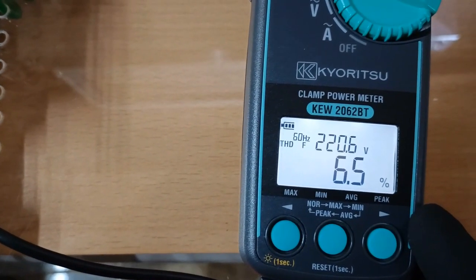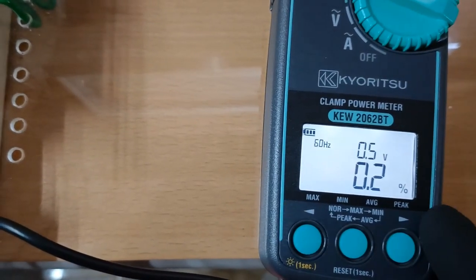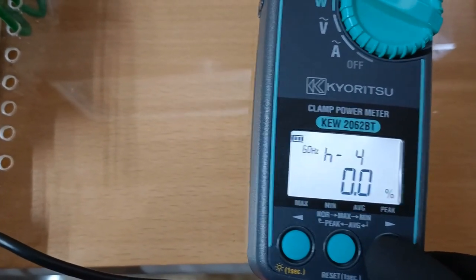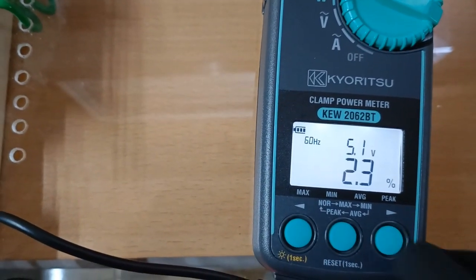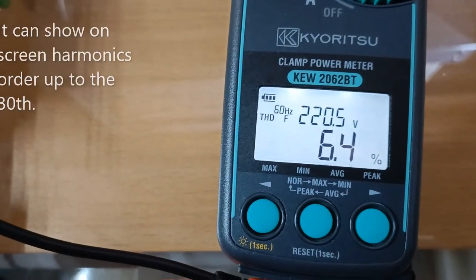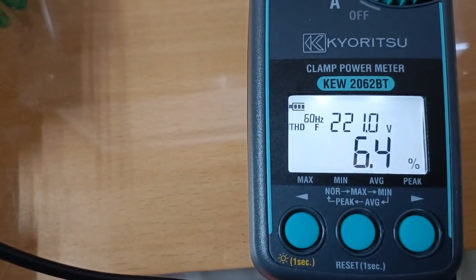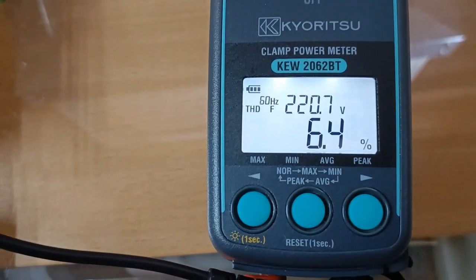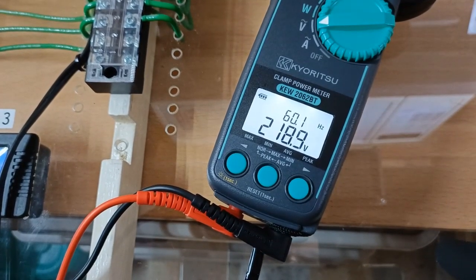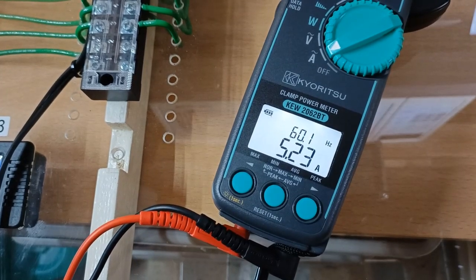For the voltage we have a 6.5 percent total harmonics distortion as a percent of the fundamental wave. Second order harmonics is 0.3 percent, third order 6 percent, and fifth order 2.3 percent. The harmonics order here can go up to the 30th order, but for single-phase loads usually the third, fifth, or sometimes seventh harmonics order are the most predominant. We can also individually measure voltage on its own — that's 218 volts true RMS at 60.1 Hz. For current that's 5.23 amperes true RMS at 60.1 Hz.